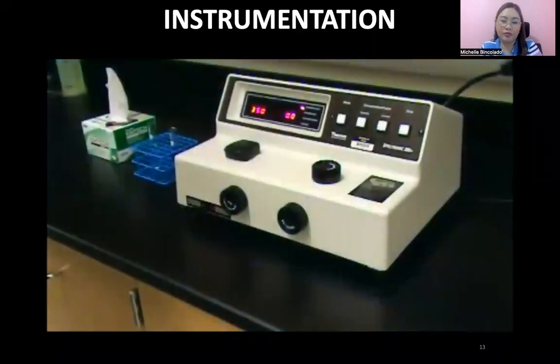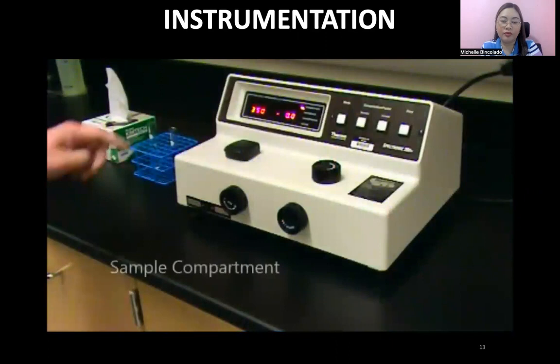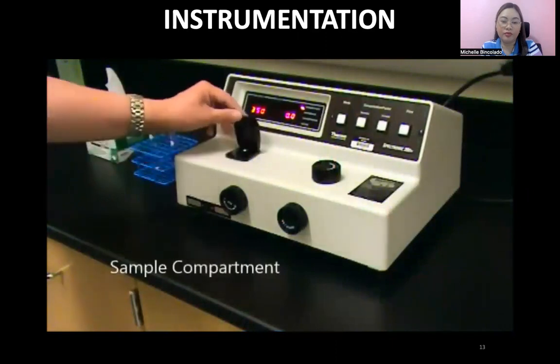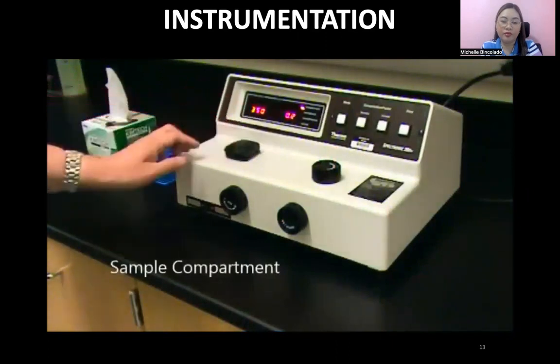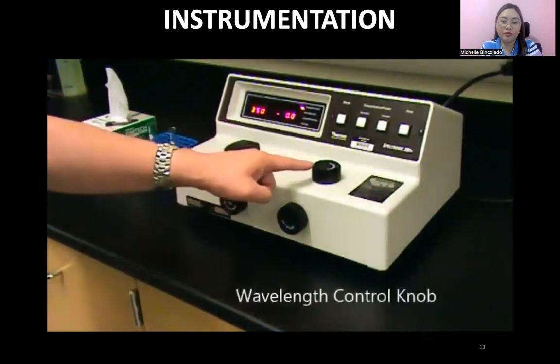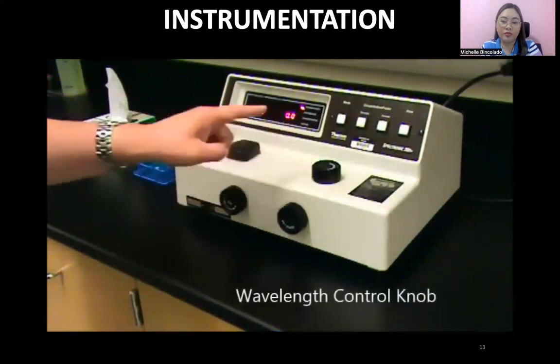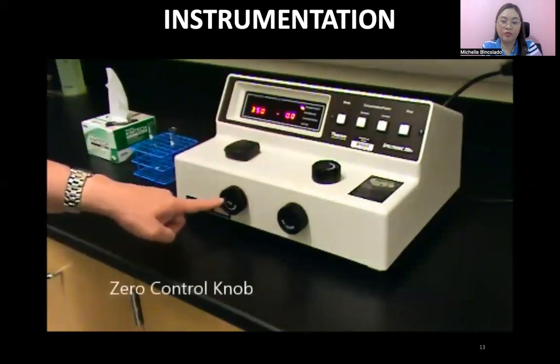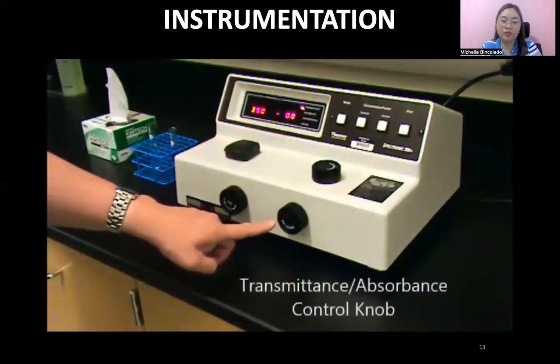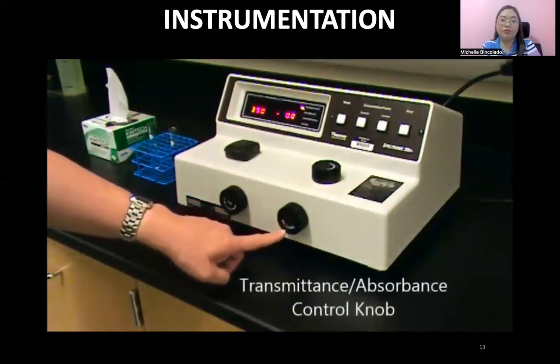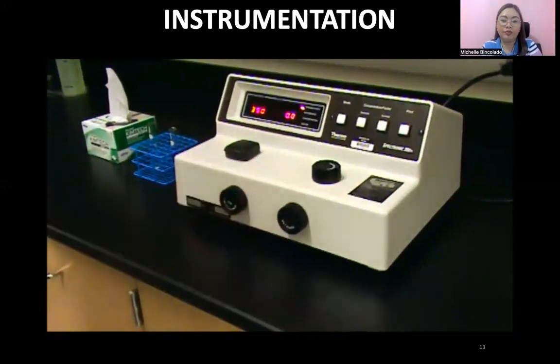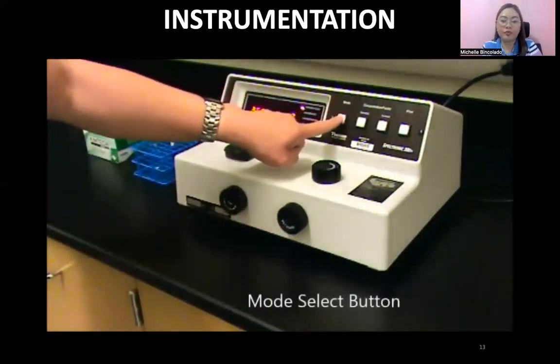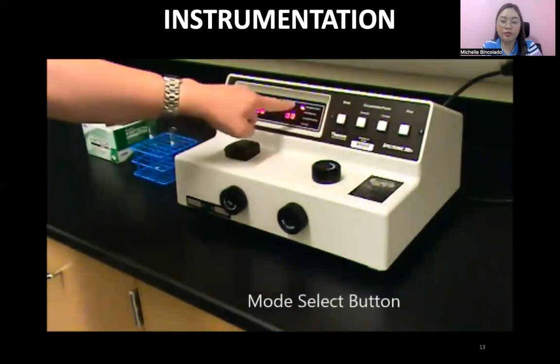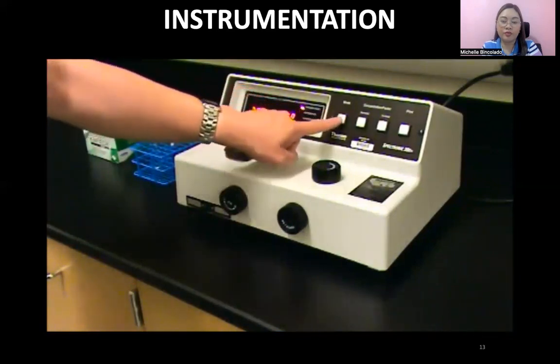First, let's go over the parts of the spectrophotometer. First, you have the sample compartment. The lid opens and closes to put your sample inside. You have the wavelength control knob to change the wavelength. This is called the zero control on the left-hand side. And this is the transmittance absorbance control on the right-hand side. Right on top is the mode select button. And when you push the mode select button, you'll notice that the LED will change positions. And so will the readout.